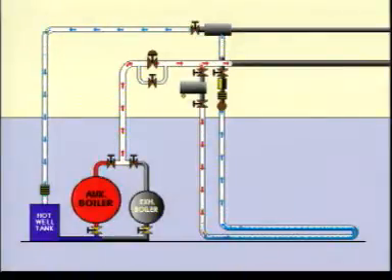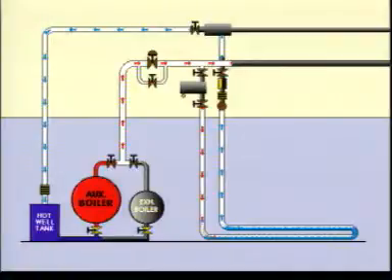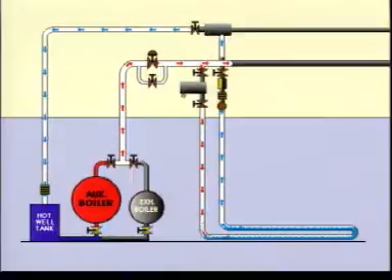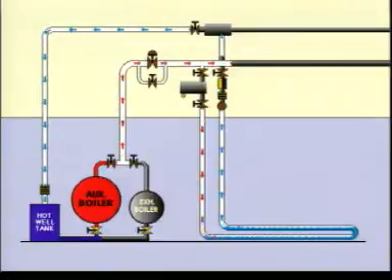Depending on the pressure in the coils, the temperature of the steam will be between 110 and 165 degrees centigrade. This particular system is built to work with a maximum pressure of 10 kilograms per square centimeter.